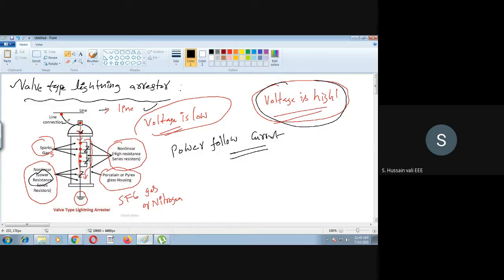So the entire current takes this path rather than going to the system. It won't go to the system; instead it goes through the air gap and the lower resistance into the ground, when the voltage is high. Once this conducting path is created, that current is called power follow current, present whenever the gaps are conducting through the sparks.